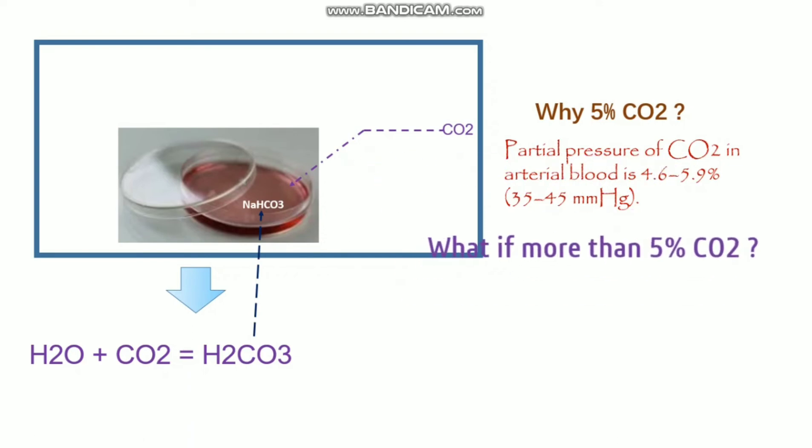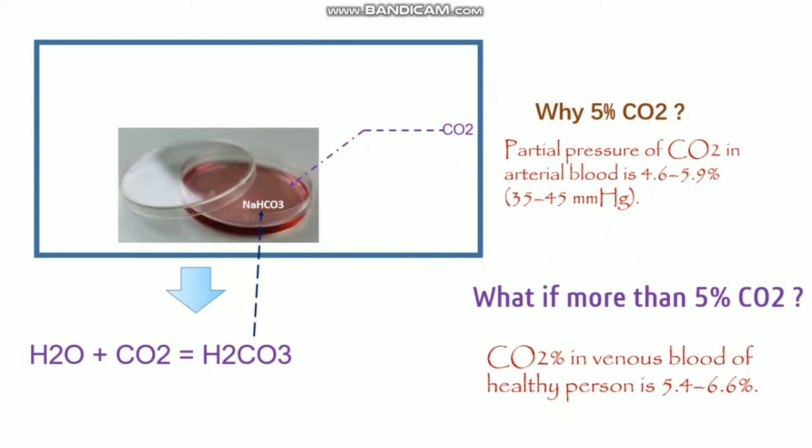Next question: what if more than 5% carbon dioxide? That is also an important question. The carbon dioxide percentage can be varied, can be set depending on experimental purpose. For example, venous blood of a healthy person is around 5.4 to 6.6%, and also some cell lines require higher percentage of carbon dioxide for better growth, around 8 to 10% carbon dioxide. Suspension cells in some cases require higher percentage of carbon dioxide. This carbon dioxide percentage can be varied and set according to your experimental purpose.